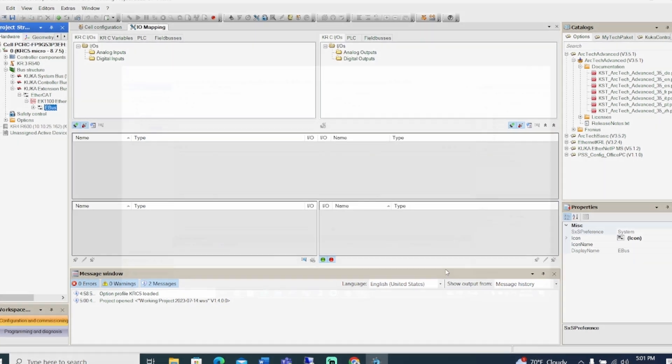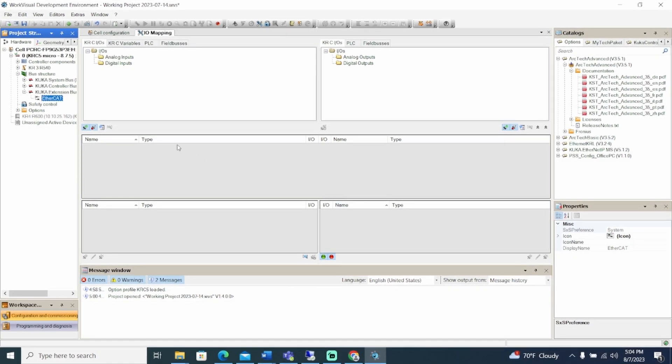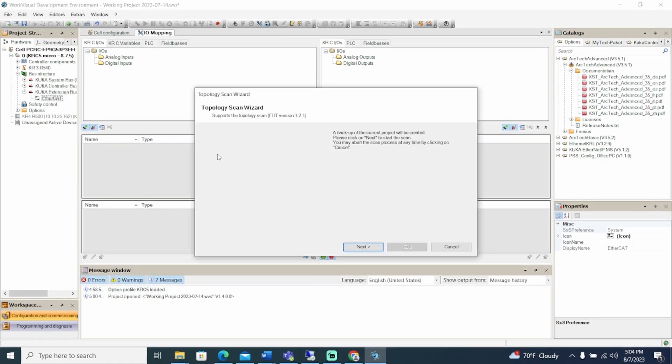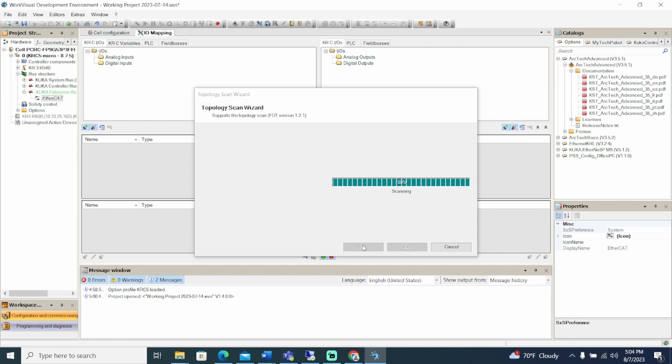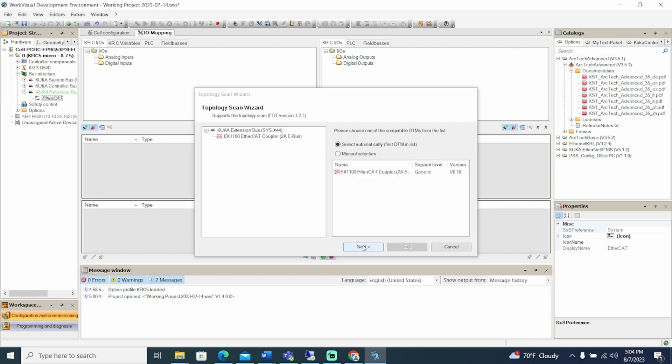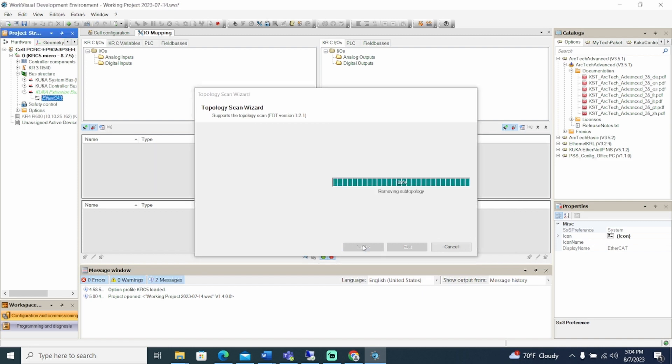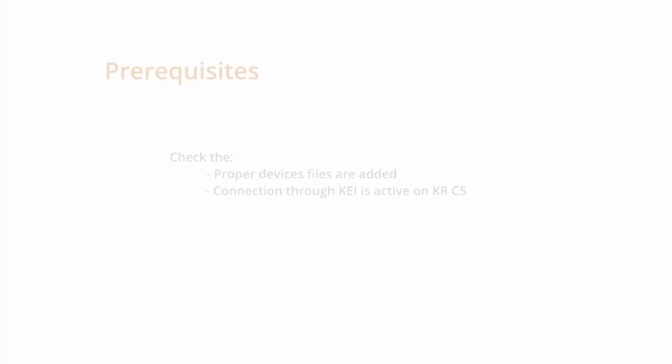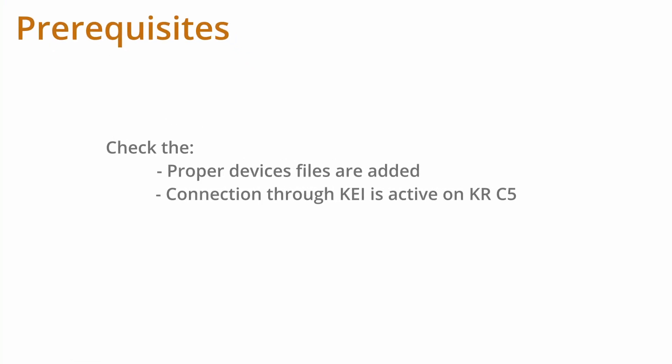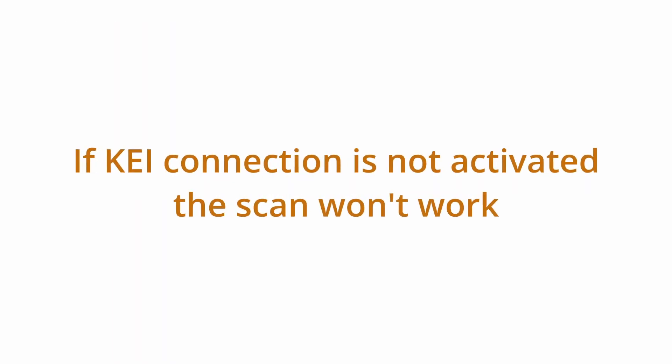As an alternative, click EtherCAT and select Scan Topology. Confirm prompts by clicking Next as the bus structure adds one device after another. Click Exit after the scan is complete to finish. For this to work, the proper device files need to be added in WorkVisual, and connection through the KEI must be active on the robot controller. If the KEI connection is not activated, the scan topology won't work.